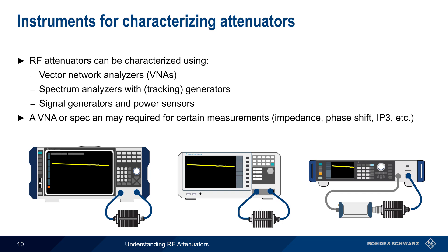It's also important to keep in mind that the instrument must have sufficient dynamic range, especially when characterizing attenuators, or cascades, with high attenuation levels.